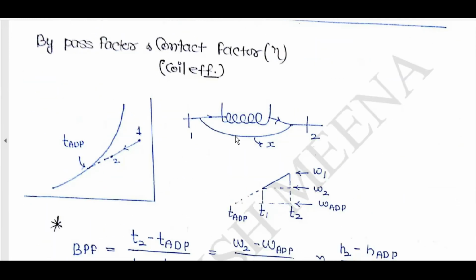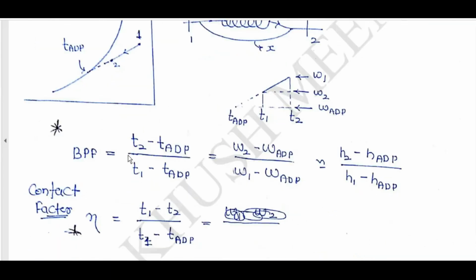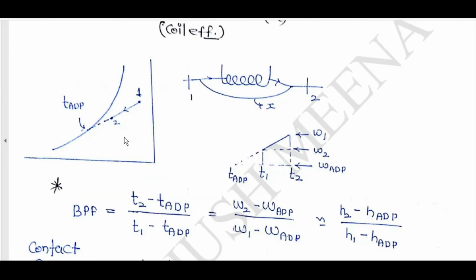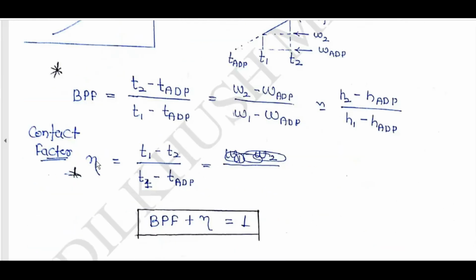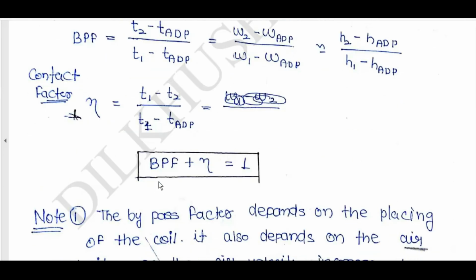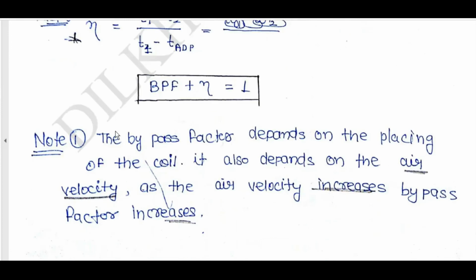Bypass factor or contact factor, eta, coil efficiency. For process 1 to 2, BPF, the bypass factor, is equal to T2 minus TADP by T1 minus TADP. That is maximum possible, by law; the numerator is the loss. T2 minus TADP by T1 minus TADP is equal to W2 minus WADP by W1 minus WADP is equal to H2 minus HADP by H1 minus HADP. Contact factor, like efficiency, is equal to T1 minus T2 by T1 minus TADP. BPF plus eta is equal to 1.